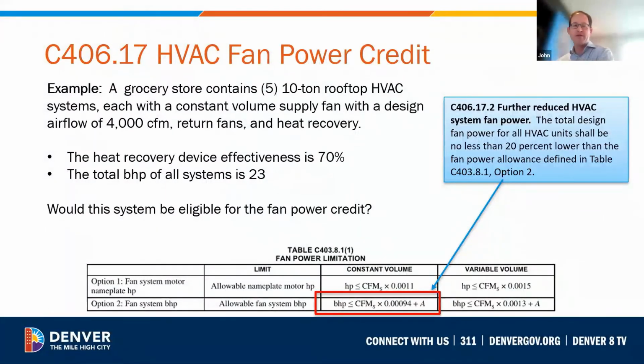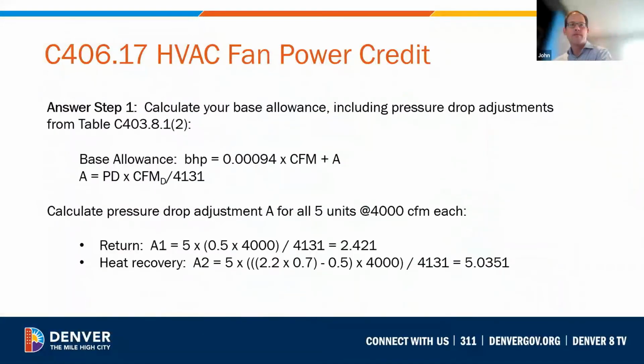So the first thing we have to do is determine what the allowed fan power is using the table and the standards, and we would use this A term for the adjustments to adjust for heat recovery. We calculate the base allowance. Again, not to get bogged down with the calculation, but to go through the methodology. We would calculate the base allowance, and we would add any pressure drops available for the heat recovery for each of these 5 units available here, and we would add that to the total fan power allowance for the brake horsepower.